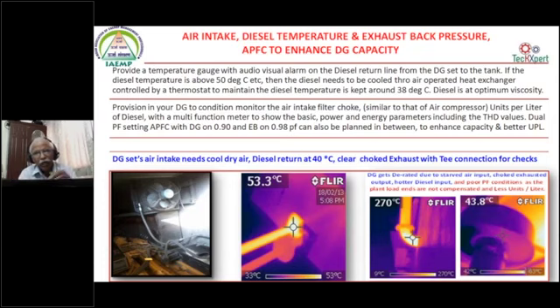The next one is the back pressure that is happening due to the exhaust back pressure. We have suggested that they remove that L joint. On this, you can see the right bottom image. We have asked the industries to remove the L joint, the long bend, and put a T connection with an inspection cover, so they can remove all the debris from the exhaust.